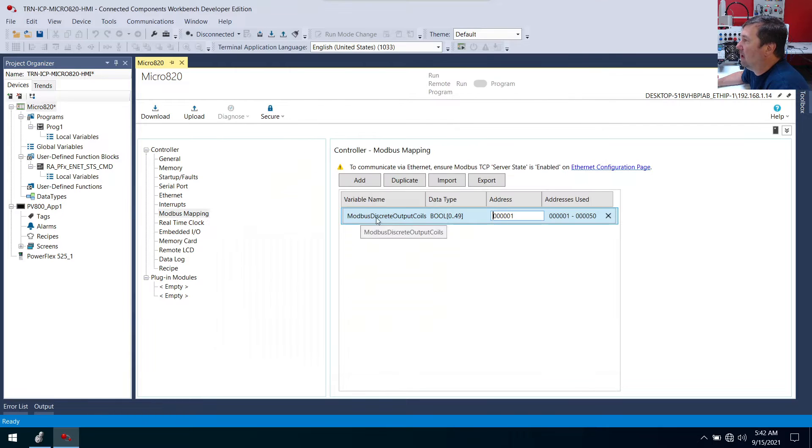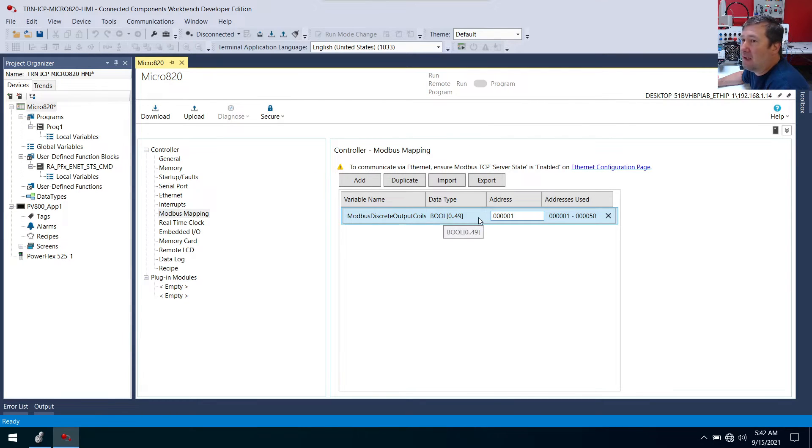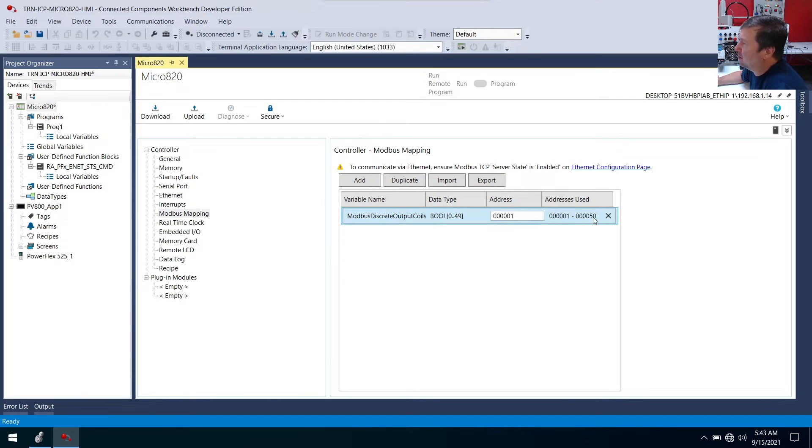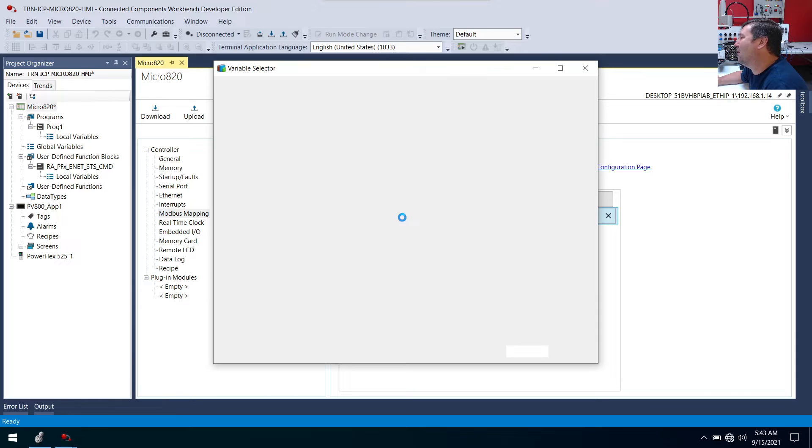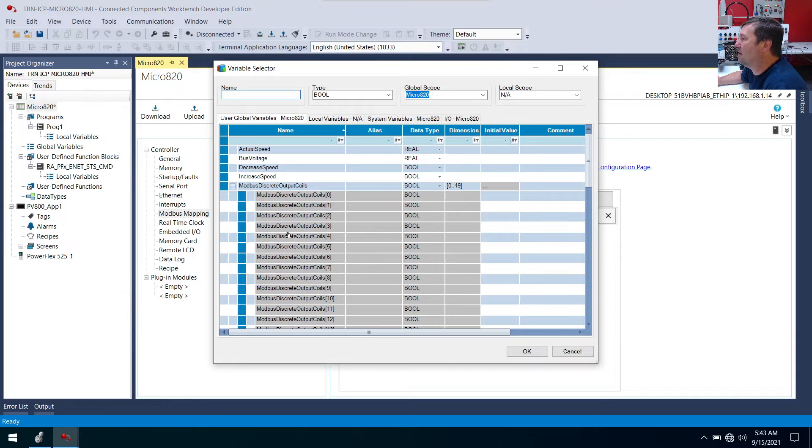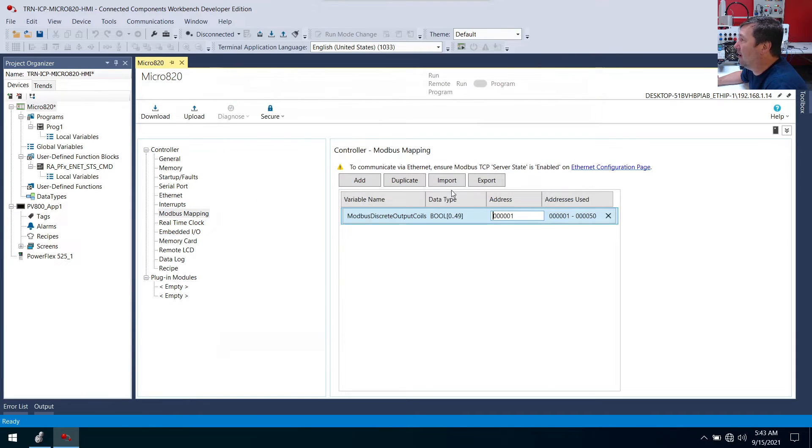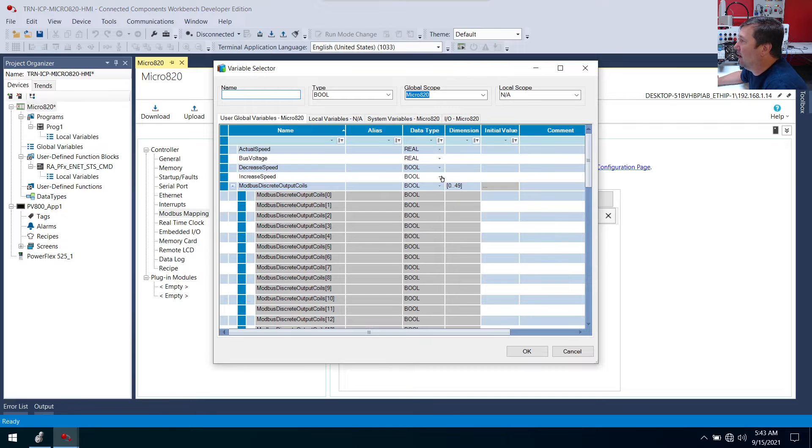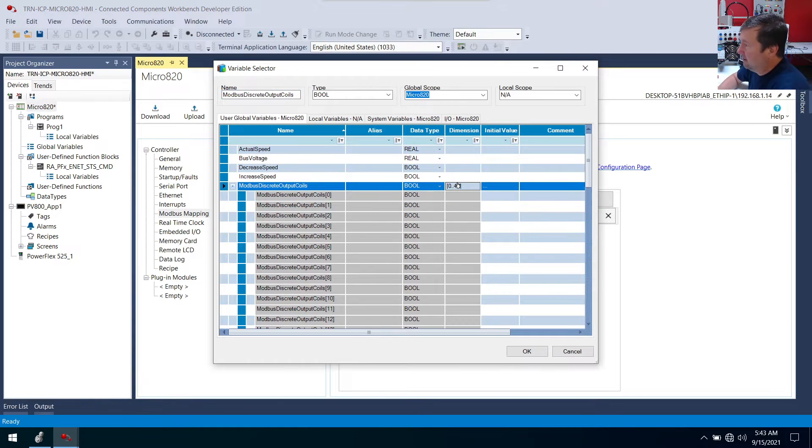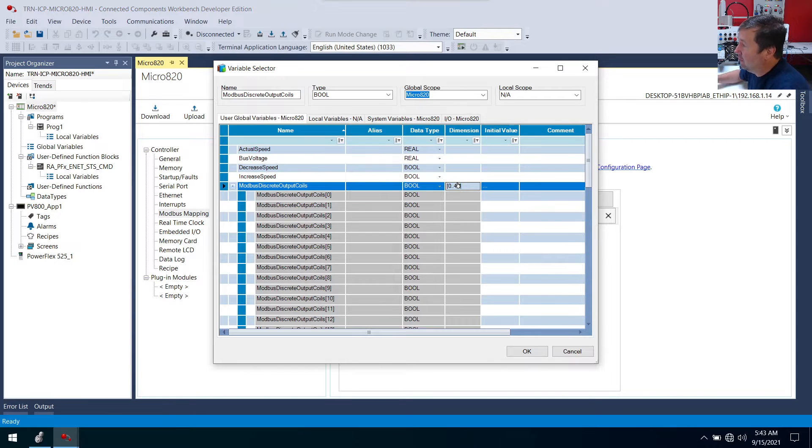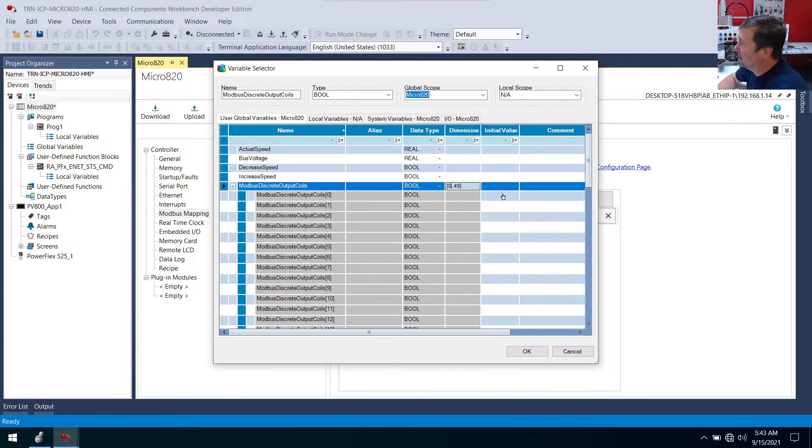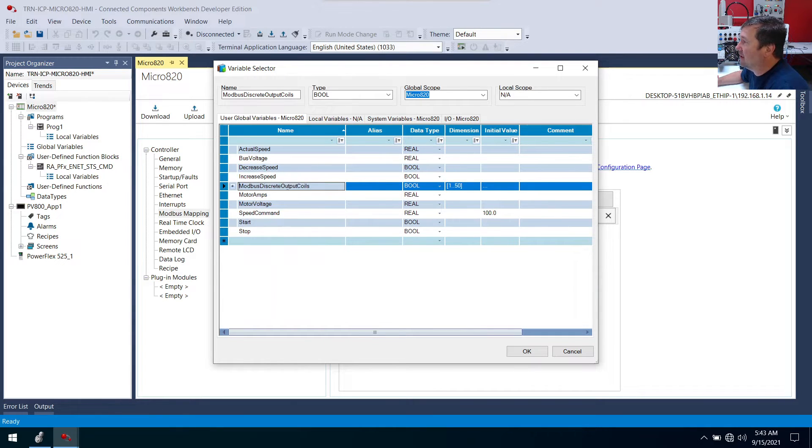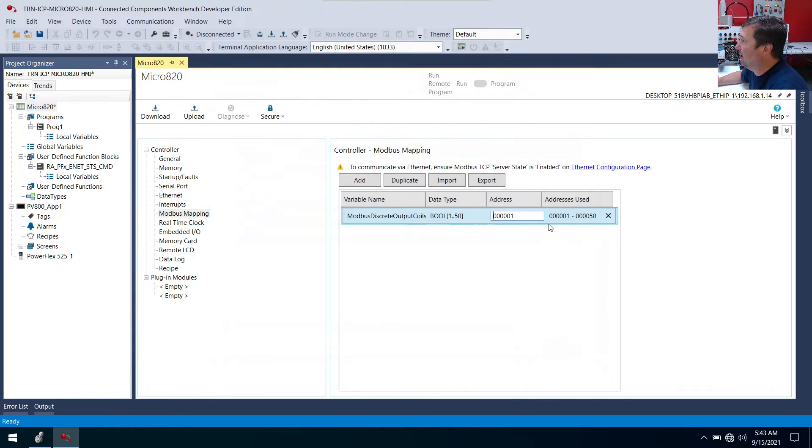Now we have Modbus discrete coils and 0 through 49. And we're going to leave this at the default. It comes up with 1 through 50. Now notice we're putting 0 through 49 in 1 through 50. That's a little confusing. So I'm actually going to double click on this. Here's one cool thing about connected components is in Studio 5000 we would start with 0. We don't actually have to do that connected components. I'm going to make this 1 through 50.